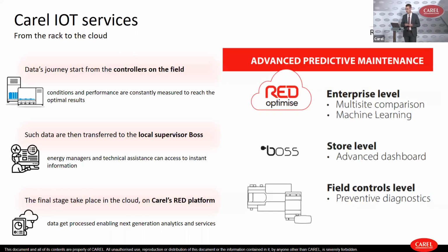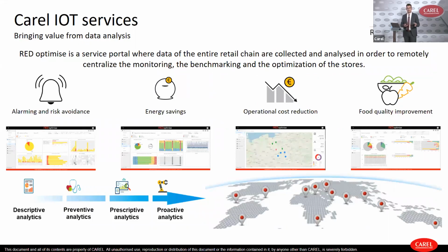So with RED, you have the possibility to compare live, if you have more than one supervisory system and of course more than one store to control. You have the possibility to compare the operating conditions of these stores and also undertake some actions. For example, you can check from the different stores if one store has more alarms than another one. So you can send the contractors, the installer, the maintenance people to check what is happening just on this site that is requiring assistance, instead of programming a lot of visits to all the sites.